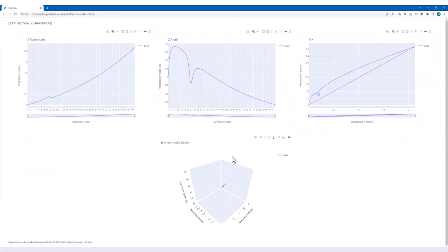Now let's take a look at bus 2 in plot analyzer. We'll select the output report, which was the harmonic frequency scan I just performed. You will notice that the plots include the Z magnitude, which you are able to see the possible resonance point with the peak again, the Z angle, a two-dimensional Rx diagram, and a three-dimensional Rx versus harmonic diagram. And you can rotate it and see it from different angles and do further analysis regarding it.